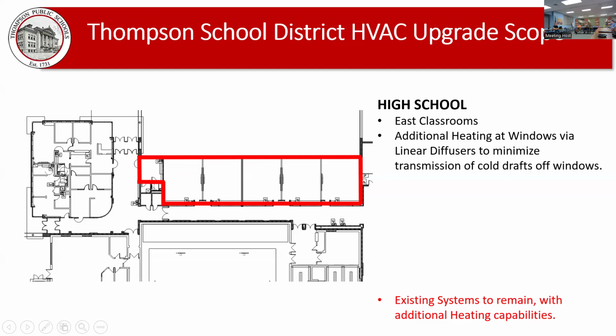So from an original design perspective, we have nothing at this perimeter wall. Even with a thermal break and very efficient windows, we still don't have air movement getting into that zone. It's all coming back toward the corridor and leaving, satisfying the thermostat, not really reaching that space - like a bungee cord coming right back. So it's a double effect in these rooms with radiant heat panels against the wall.